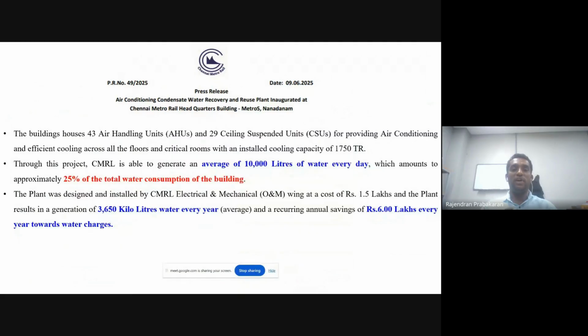Chennai Metro Rail Corporation installed, in their building, 43 air handling units and 29 ceiling suspended units for providing air conditioning and effective cooling across all the floors and critical rooms. The total capacity is about 1,750 TRs. In this 1,750 TR capacity unit, about 10,000 liters of water was produced from the condensate every day. This 10,000 liters of water they have used for other purposes in the building. With that, they are able to save 25% of the total building water consumption, and also save around 6 lakh rupees per year in additional water charges.